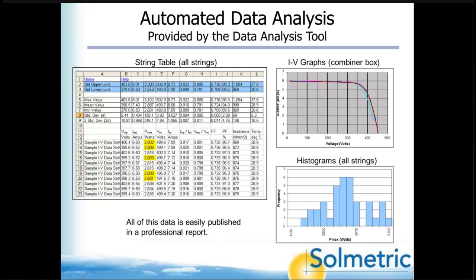If you set allowable limits in blue, it will tell you which strings are not acceptable. In the upper right, for each combiner box, you get a family of IV curves. In the lower right, for each parameter, like Pmax, you see a histogram or frequency distribution plot showing how closely your values are clumped together, with each count on the vertical axis representing one string.